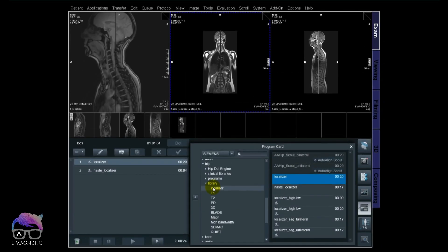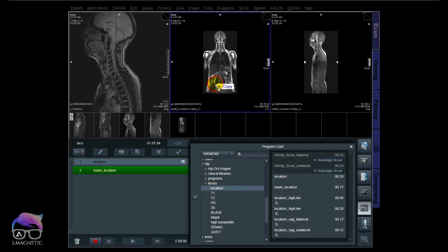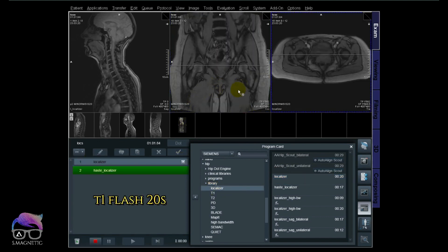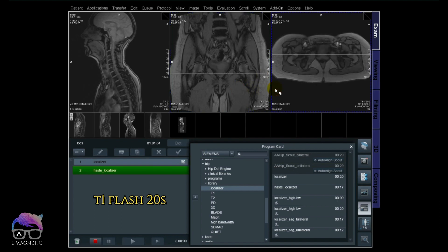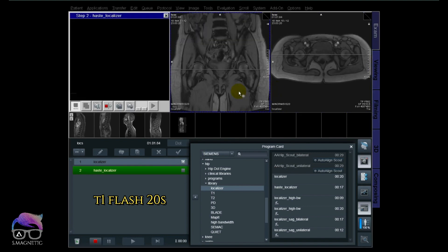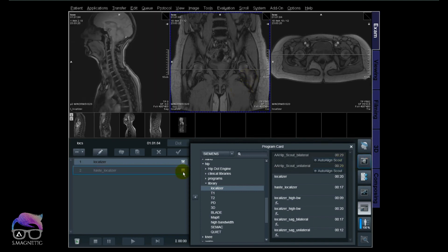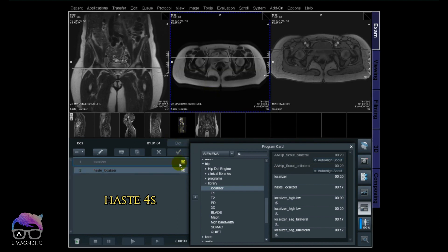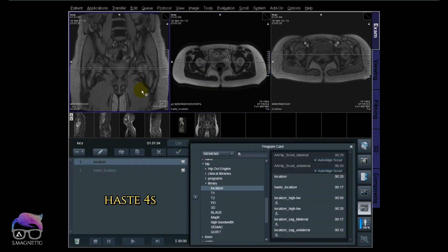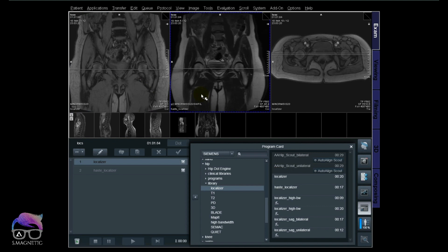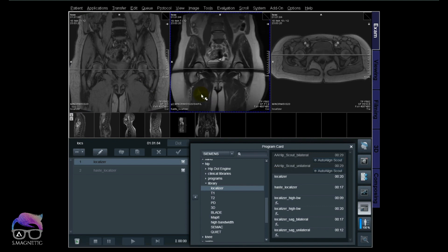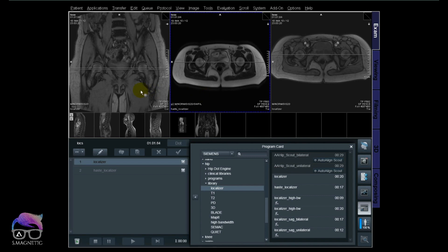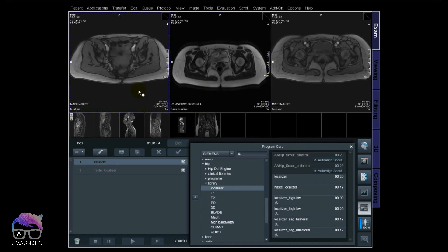Then let's move further down to the hip. This is the original one from Siemens, it takes around 20 seconds. And then I modify one HASTE localizer, which takes around 4 seconds. So it shows here the coronal plane and transverse plane, which is great. You see the anatomy for further planning. Let's run the HASTE localizer. I also did the same here, lower the TR and the flip angle. It's not that bad for 5 seconds or 4 seconds, just to see the anatomy for further planning.